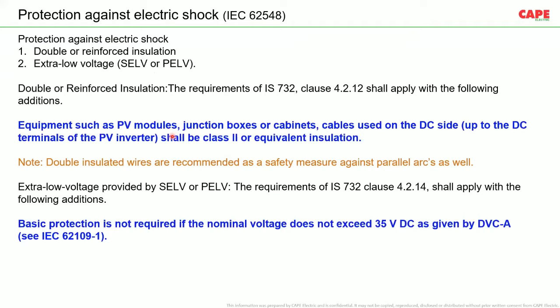Protection against electric shock. As you know, for every electrical installation, there are four protective measures required. First is protection against electric shock. Second is protection against thermal effects. Third is protection against overcurrent and overload. The fourth one is overvoltage protection. With respect to electric shock, it is very important to understand that the protective measure, fault protection by protective equipotential bonding and automatic disconnection of supply, is not practical. The recommended method is double or reinforced insulation.